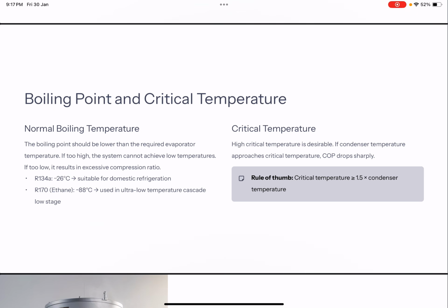For example, if I want to achieve domestic refrigeration, wherein I need to maintain the system temperature below 0 degrees centigrade, then the refrigerant should boil at a lower temperature than the evaporator temperature. So, for example, R134A, which boils at minus 26 degrees centigrade, would be suitable for domestic refrigeration. Similarly, if you take another application, like achieving minus 80 degrees centigrade in an ultra low temperature cascade system, the choice of the refrigerant cannot be R134A because we need a boiling point lower than the required evaporator temperature. So for that, ethane, which is R170, becomes the obvious choice.